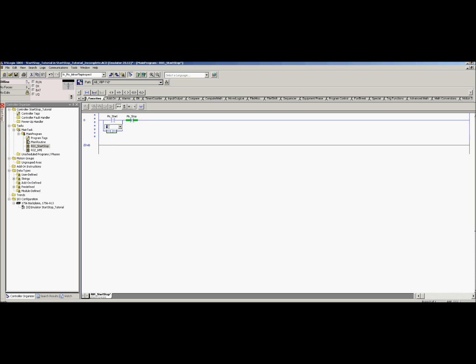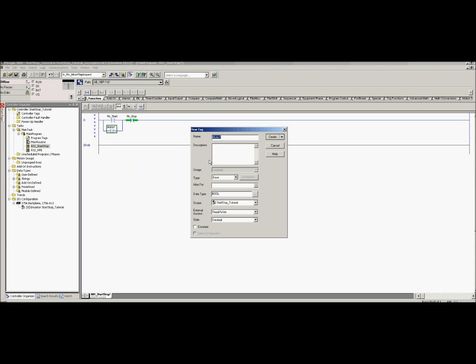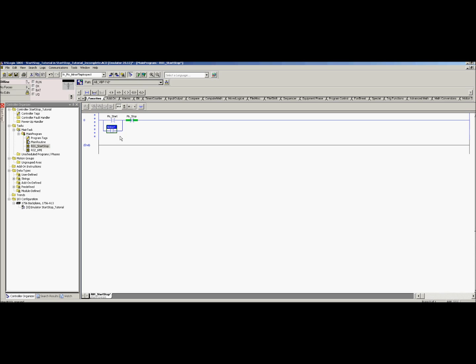Now we're going to put another XIC for the holding contactor, and I'm going to call this 'motor1' — new global tag, create. Once you name something you can use it again as many times as you want throughout the whole program. We are going to make a coil — OTE, Output Energize, that's what OTE stands for. Since it's a global tag, if this output energize is on, that tag will be high everywhere in the whole program.